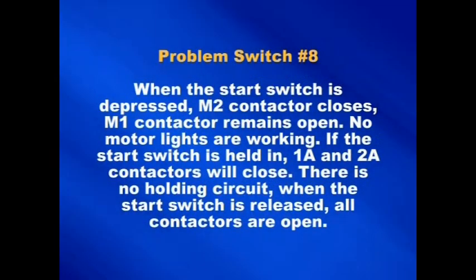Should the apprentice electrician draw a problem card number 8 when he goes to the testing center, this is what he'll have. When the start switch is depressed, M2 contactor closes, M1 contactor remains open. No motor lights are working. If the start switch is held in, 1A and 2A contactors will close, but there's no holding circuit. When the start switch is released, all the contactors open.